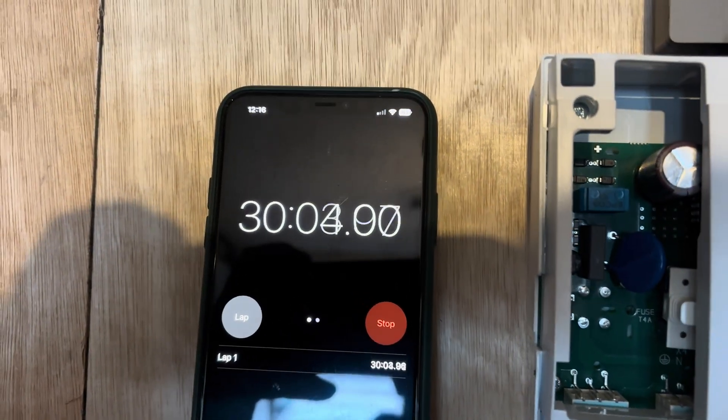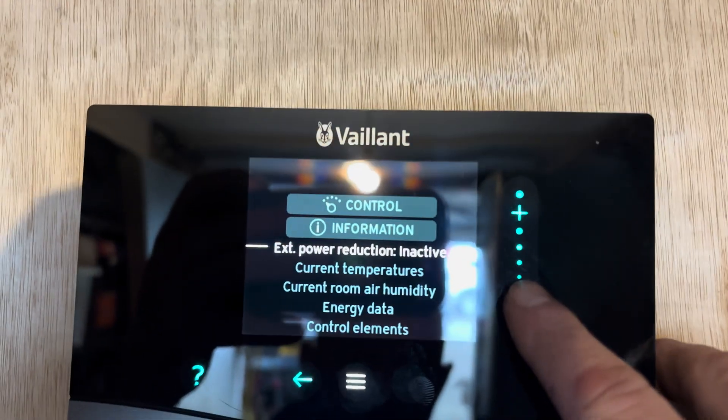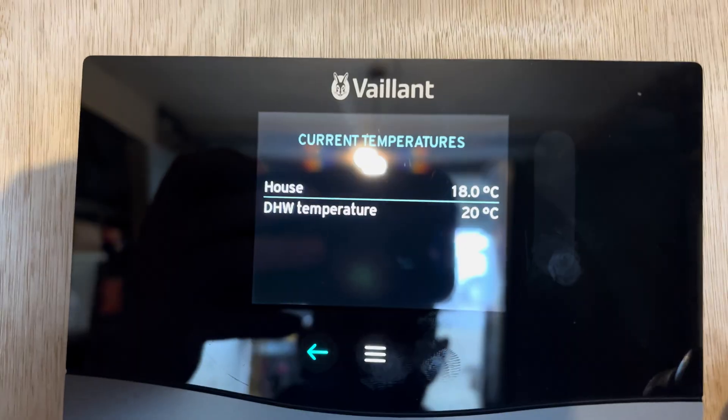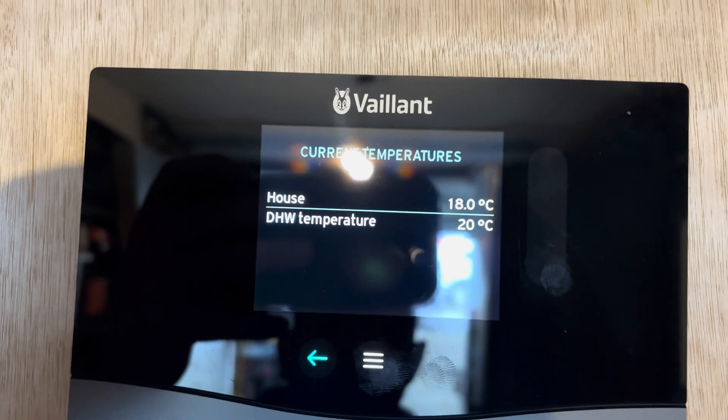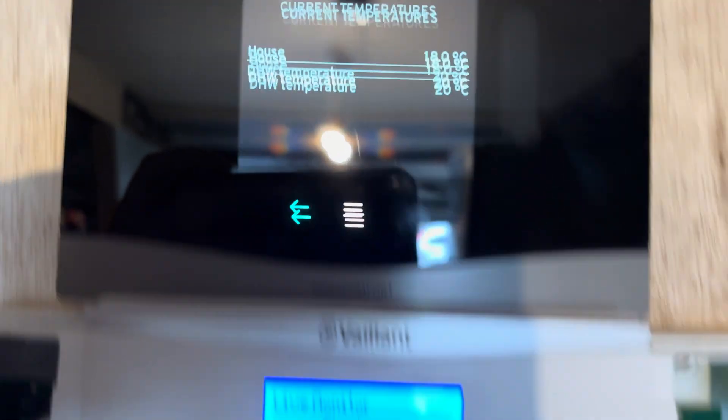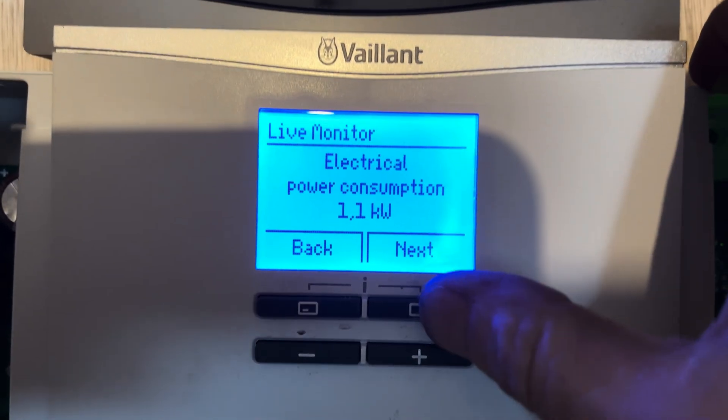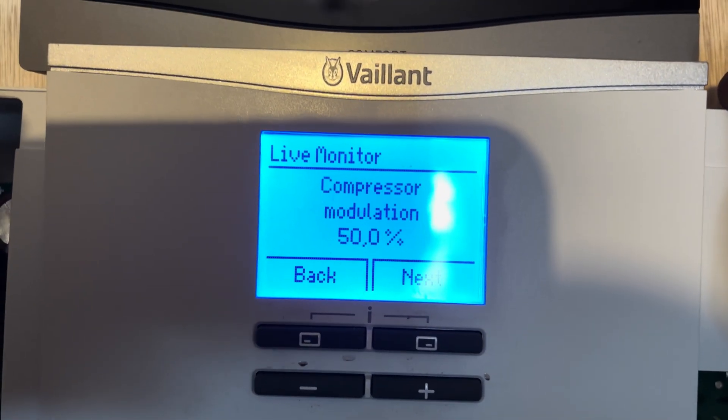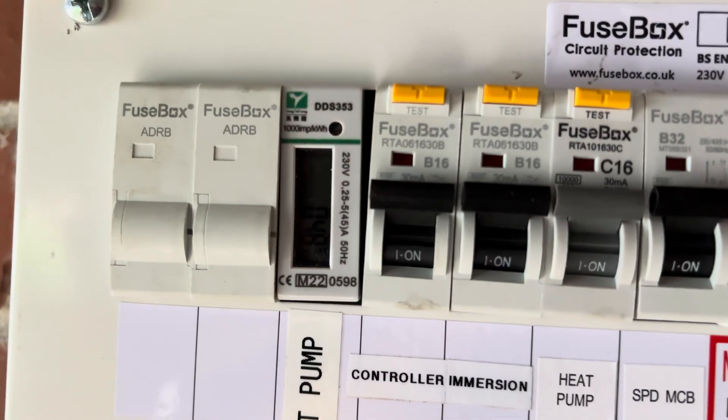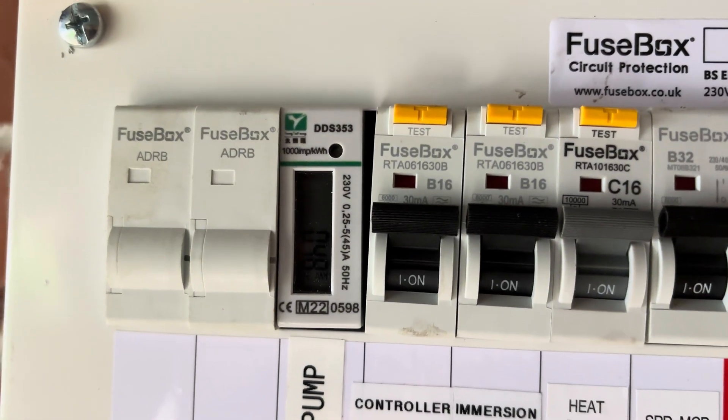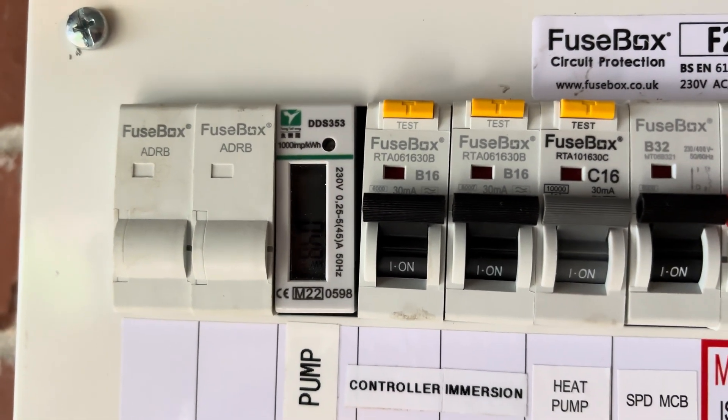So we've been running for 30 minutes now. We started at 11 degrees C in the hot water cylinder. We're now at 20 degrees C. So a 9 degrees C increase. 1.1 on the power consumption. Modulation still at 50%. Electric meter now is reading 0.48 kilowatts.